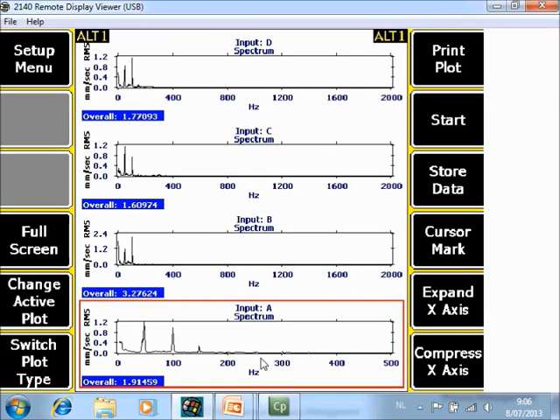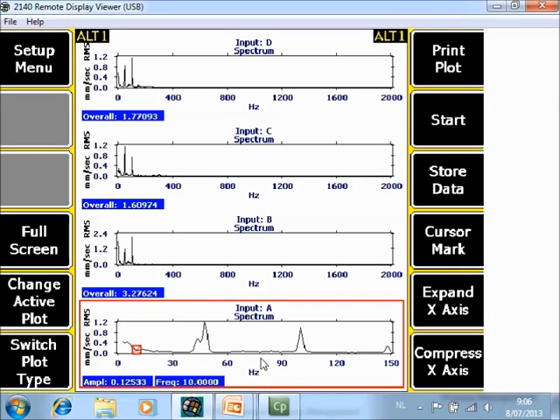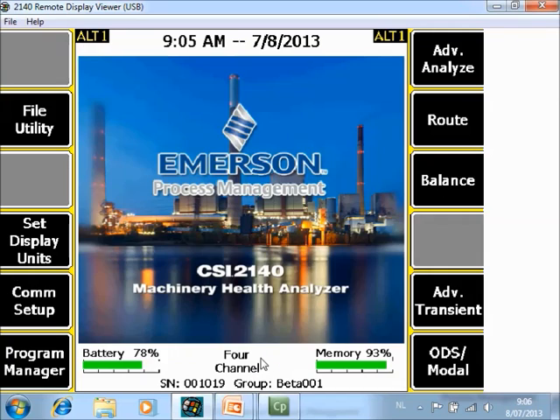When I now expand the peak, you can see this was the imbalance value. But the imbalance value is not one peak — it is multiple peaks because the speed changed during data collection, and the amplitude of all those peaks is wrong. So more or less this spectrum is completely wrong. Now let's look at how to do order tracking — starting from the home screen.